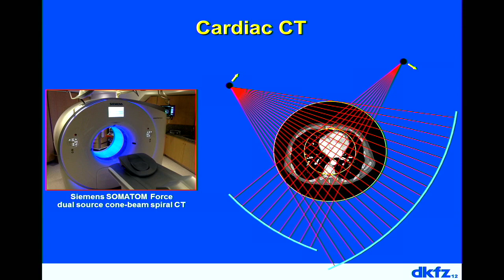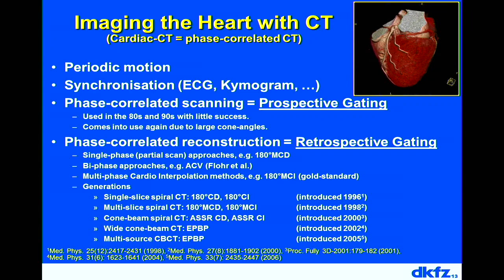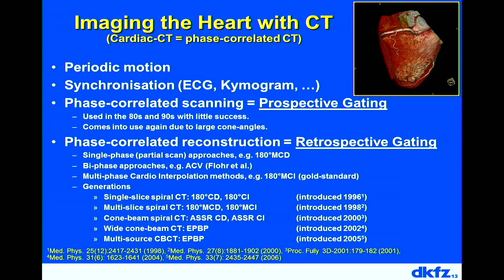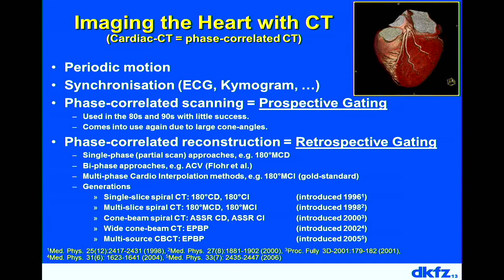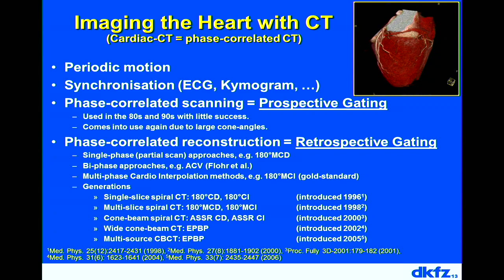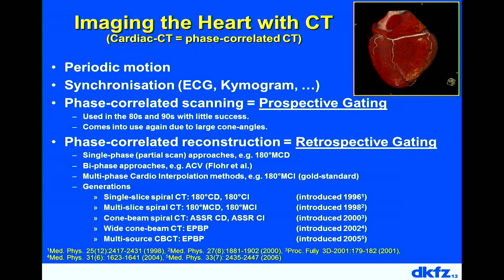To image the heart, one must assume it is quasi-periodically moving, since images from different heart cycles are typically stitched together. We use the ECG signal to know when the patient has systole or diastole. You can either start the scan at a desired moment — called prospective gating — or acquire data freely and decide during reconstruction which cardiac phase to use, for example diastolic data — called retrospective gating. Both techniques are in use today.